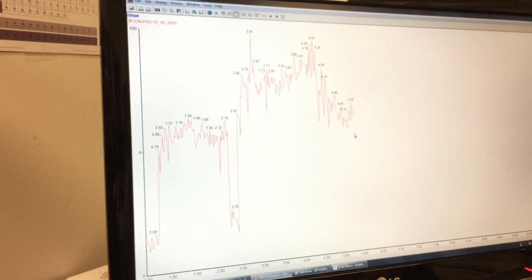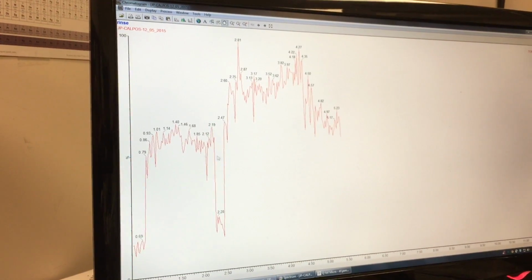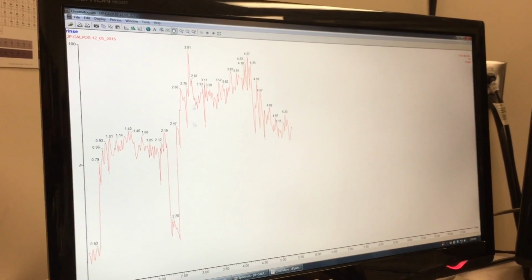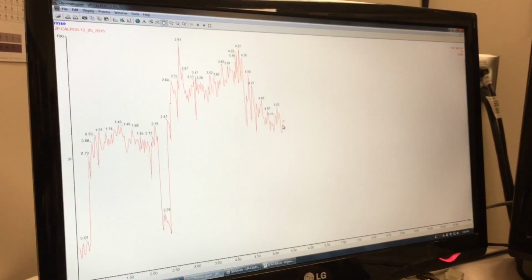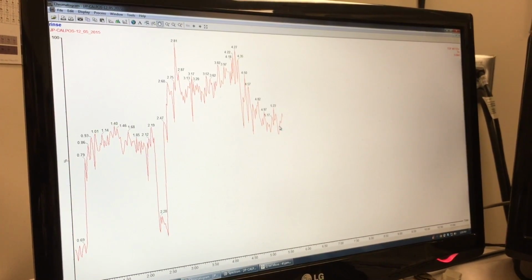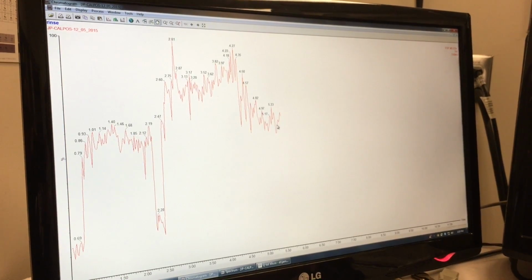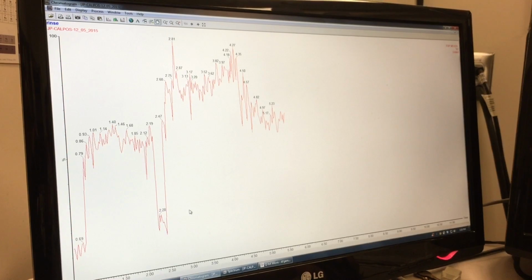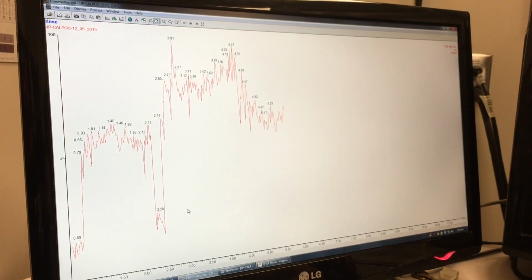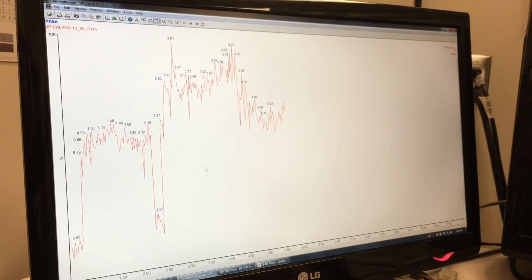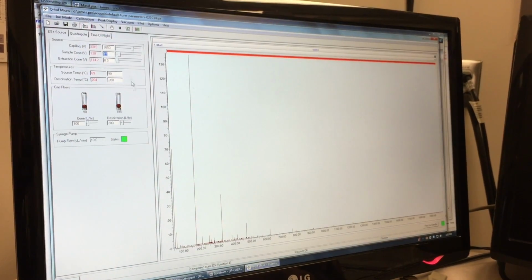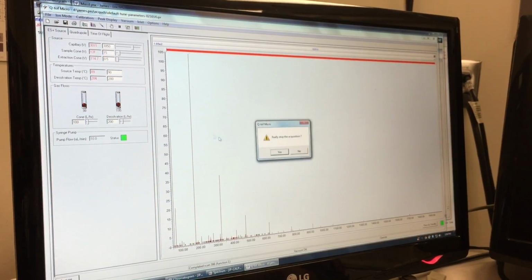So as you can see, we've been collecting data for about 6 minutes, which will be great for ion resolution, and some of these fluctuations in the total ion count are due to some of the adjustments we've made on both our home screen as well as the XY source adjustments. Once you're ready, you can stop the acquisition.